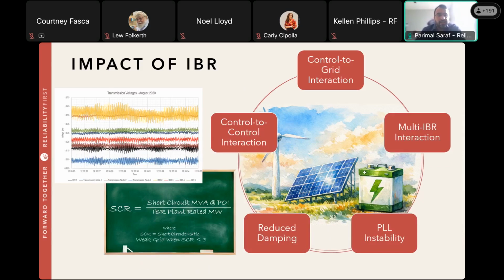So other than inertia, there are several other newly found behaviors that these IBRs reflect in the system that have not been seen in the traditional electric grid. So before I move into the details of these phenomena, I want to talk about a couple of items. First thing is SCR, that's called the short circuit ratio. It's essentially a representation of the strength of the electric grid, and it basically tells how stiff the voltage is in that portion of the grid. And the other item I want to talk about is PLL. That's called phase lock loop.